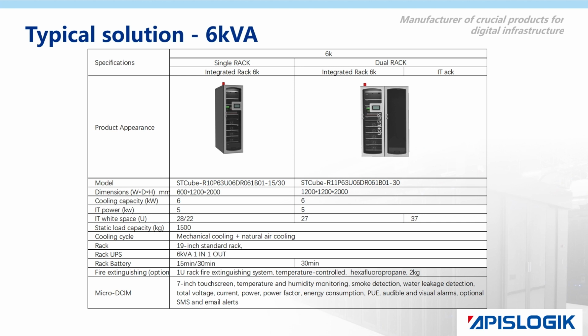2. Dual rack 6K solution, equipped with one Summit Pro rack-mounted energy-saving air conditioning unit with a cooling capacity of 6 kilowatts in each cabinet. The two cabinets provide a total of 64 U of white space. It can be customized according to requirements for backup battery runtime, optional rack-mounted gas fire suppression device, and optional cloud services. Single-phase power input.